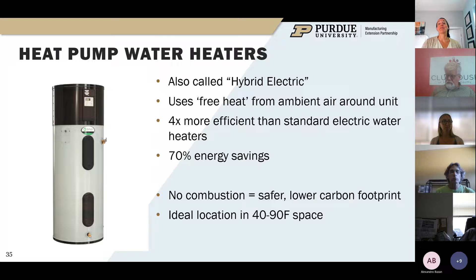One thing to note on these heat pump water heaters: because they're so efficient at pulling ambient heat, they will cool the room they're in. Ideally you want it somewhere between 40 and 90 degrees. I have one installed in my home, and I actually keep the mechanical room door open because otherwise it gets so chilly in there, since it's pulling so much heat from the ambient space and it's in the basement, which isn't a warm space to begin with. If I had to do it over, I'd put it in the warmest room of the house so it would be even more efficient.